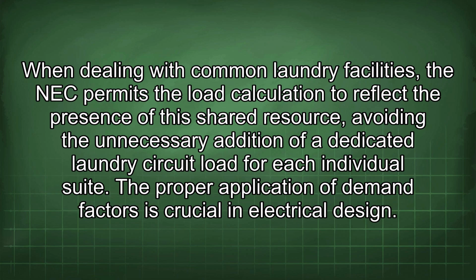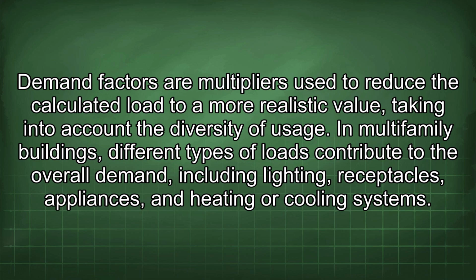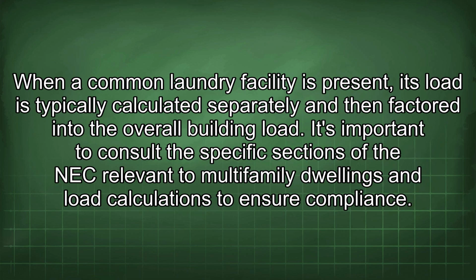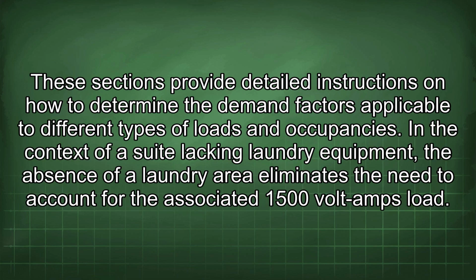The proper application of demand factors is crucial in electrical design. Demand factors are multipliers used to reduce the calculated load to a more realistic value, taking into account the diversity of usage. In multifamily buildings, different types of loads contribute to the overall demand, including lighting, receptacles, appliances, and heating or cooling systems. When a common laundry facility is present, its load is typically calculated separately and then factored into the overall building load. It's important to consult the specific sections of the NEC relevant to multifamily dwellings and load calculations to ensure compliance.